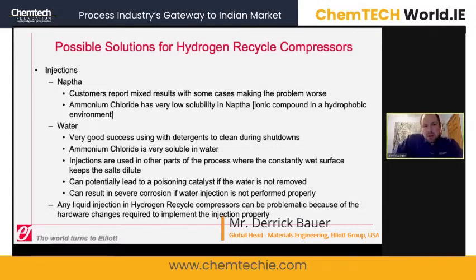Water could also be used. Water injections are used sometimes to keep the process temperature down, but they could be used for cleaning as well. And ammonium chloride is very soluble in water. However, the biggest problem with water is that it can actually accelerate the corrosion process, and that is certainly not something that is very beneficial. And thirdly, if a unit has been installed without liquid injection capabilities, there is a heavy amount of rework in order to put in the nozzles to apply the liquid injection at each stage of the compressor.